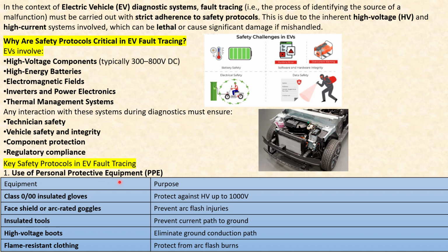Now, use of personal protective equipment. So, we will talk about the equipment and also the purpose. First is class 0 or class 00 insulated gloves, which protect against high voltage up to 1000 volts. Next is a face shield or arc-rated goggles, which prevent arc flash injuries. There have been some rare cases where technicians got blinded because of high arc flash. And next is insulated tools, which prevent current passing to ground; high voltage boots, which eliminate the ground conduction path; and flame resistant clothing, which protects from arc flash burns. Okay, so these are the various types of personal protective equipment.